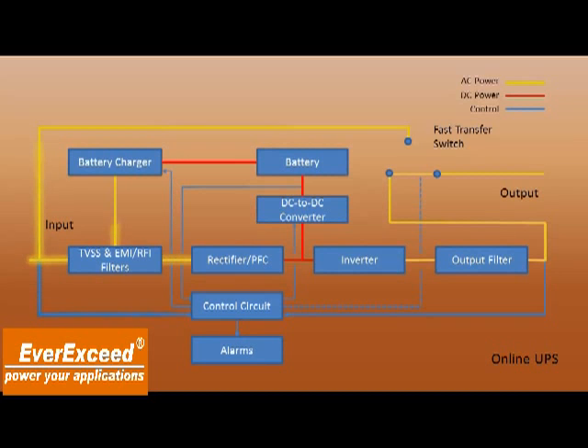When we power this unit up, we see that it provides power to the battery charger, which is not on. It goes through all the stages and provides voltage output. Notice that all the voltage provided at the output is coming through the rectifier and inverter. So this one constantly has those online. It's not just when the power goes out. There's always that total isolation between the input and the output, and the whole input power is converted to output.